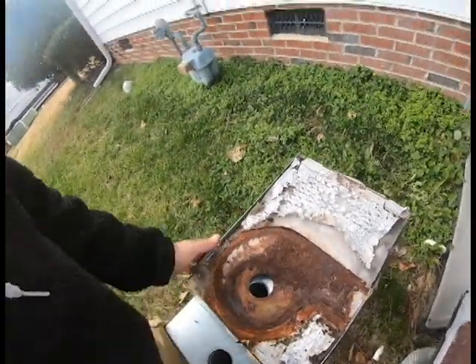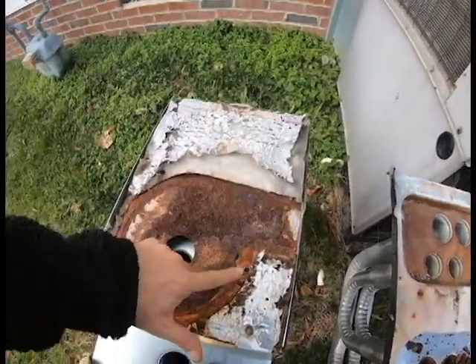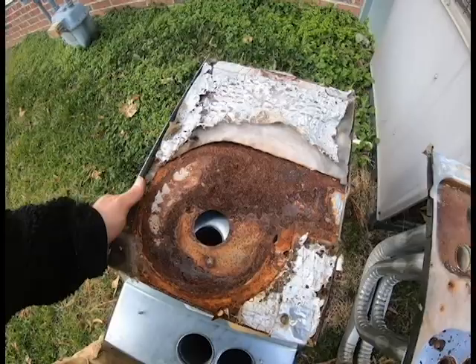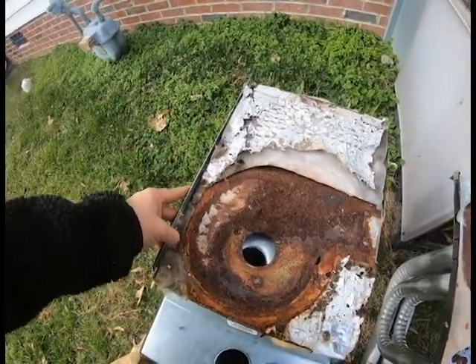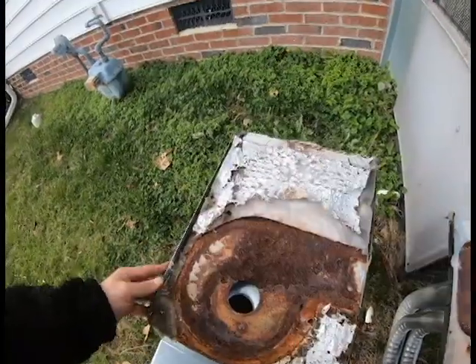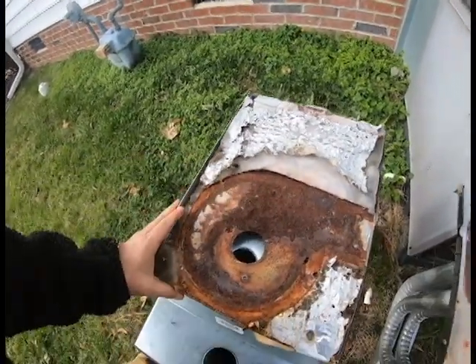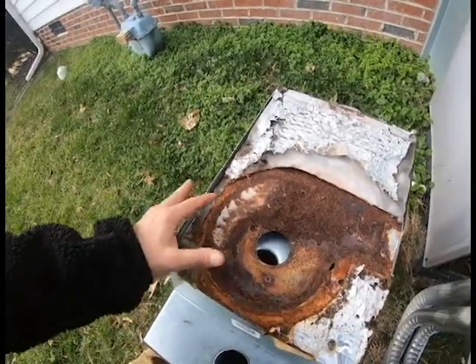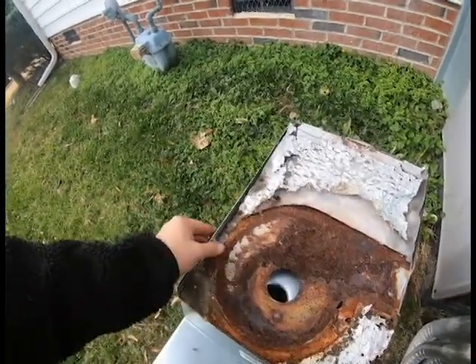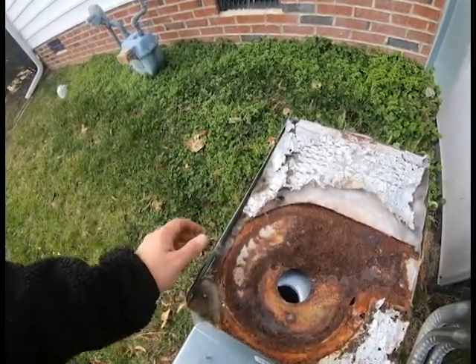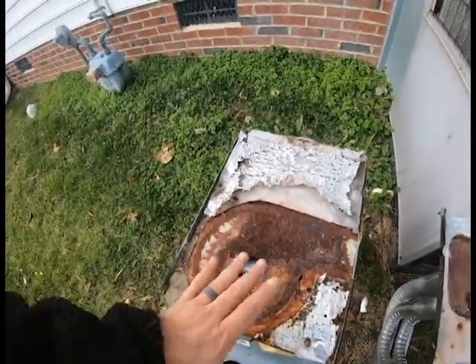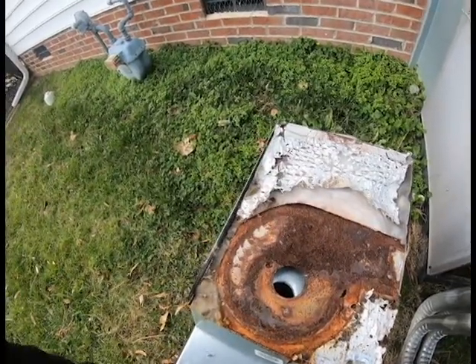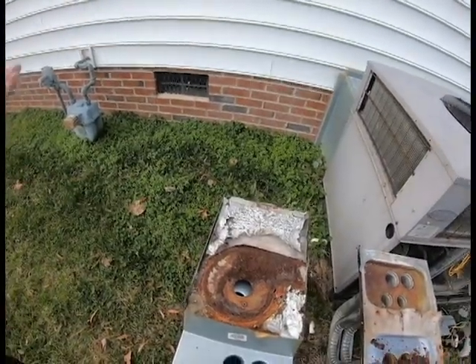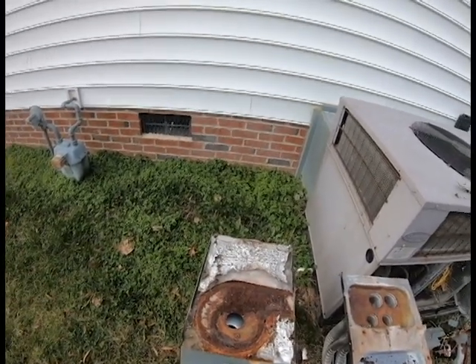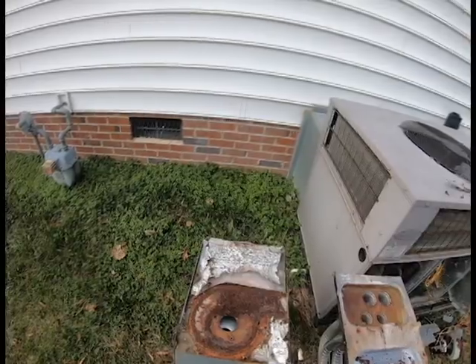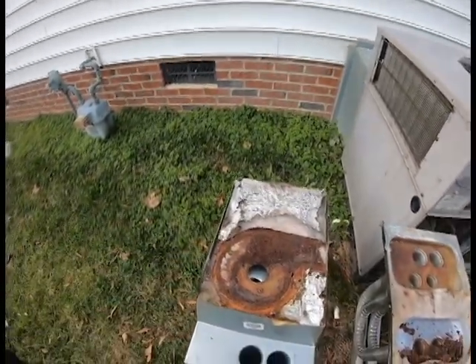Now I will tell you, this thing does not look good at all. I've made the homeowner aware of this. They're not giving us authorization to do it. But if they don't want to have it done, there's nothing we can do. So we're going to put this back in. We're going to take some high temperature silicone, put it around here for our inducer motor to make sure everything's sealed. I hate this plate. I told them it could cause problems in the future, but they act like they don't care. So as a heating and air technician, what do you do when they don't want to do it? Anyway, we'll go ahead and pop this back on and get it ready to be put in.